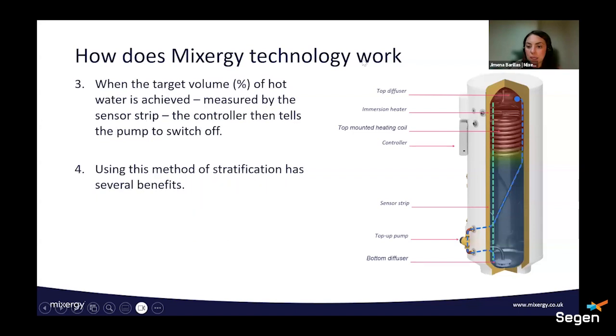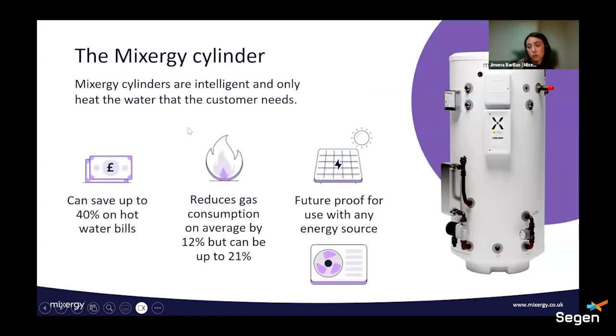As you can see here, there's a sensor strip all throughout the cylinder. So that means that when the client chooses a specific volume and the target volume is achieved, the controller then tells the pump to switch off. And that will give the client some savings in terms of money. It can save up to 40% on hot water bills. It reduces the gas consumption on average by 12%, but it can be up to 21%. And it's future-proof for use with any energy source.